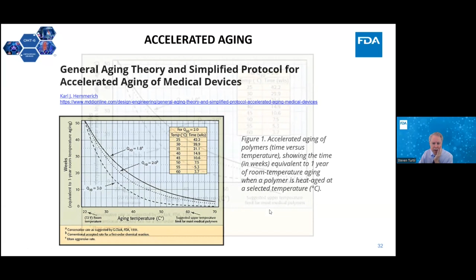This is a figure that's actually fairly commonly found, but it is in ASTM F1980. Gives you a good introduction. Accelerated aging of polymers, time versus temperatures in this flow chart, in this diagram, show the time equivalent to 1 year of room temperature aging when polymer is heat treated at a selected temperature. And to take a closer look, you can figure this out fairly easily. If you look at room temperature, in the bottom left corner, what's the equivalent in weeks for a 1 year real time? You can see, at 22, it is 52 weeks.